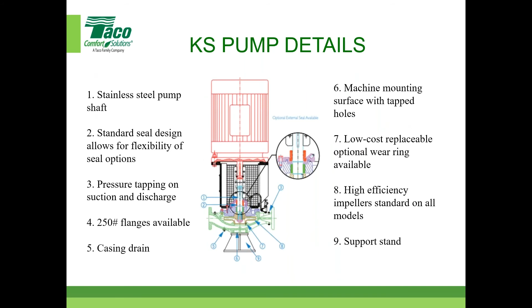Good question though. And here are the operating specifications. Again, the flange is a standard ANSI class 125, and you can see the rating there. It does go down a little bit from a pressure standpoint once you get above 150, but really it never goes below a working pressure of 150 or 140, even at 300 degrees. So something to consider there.